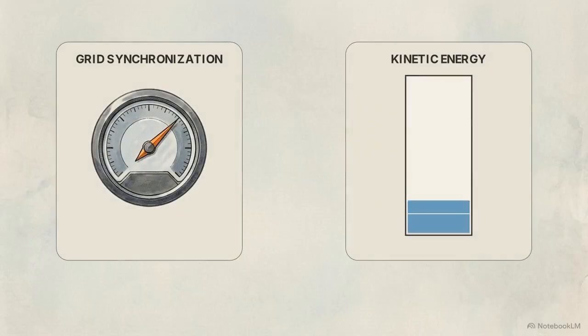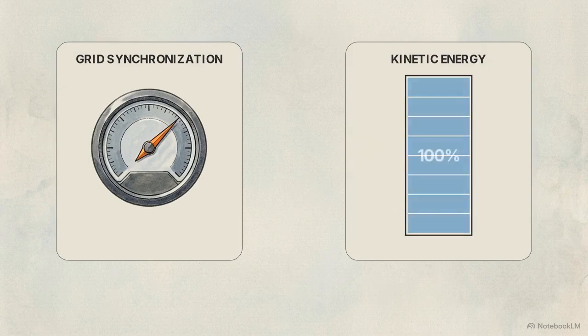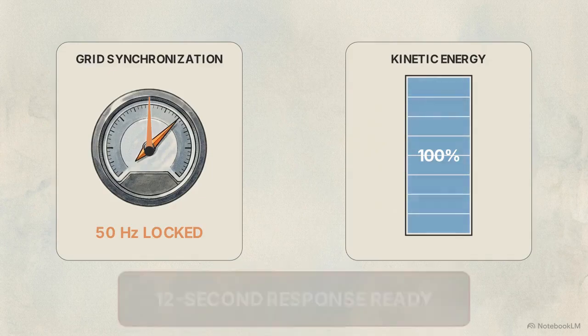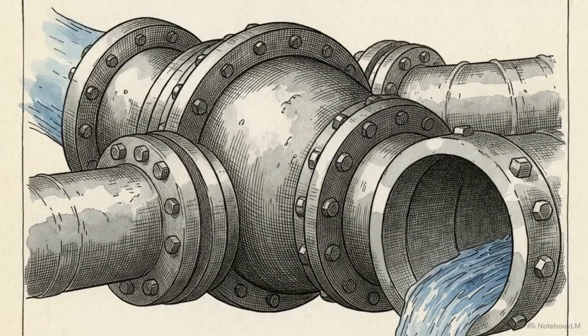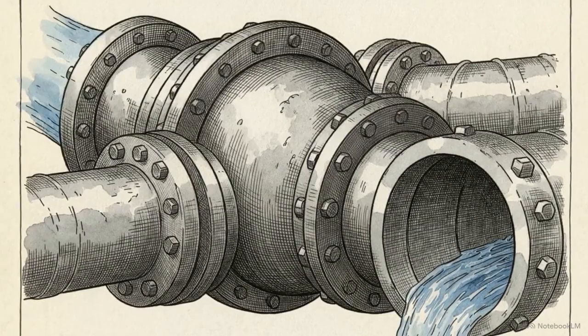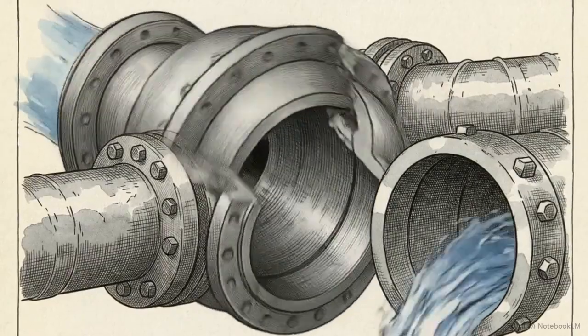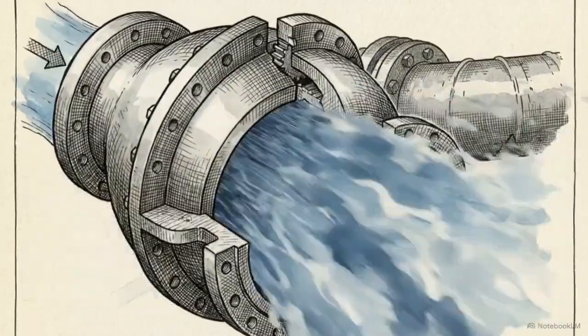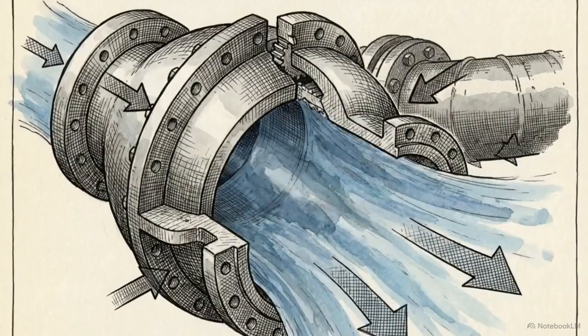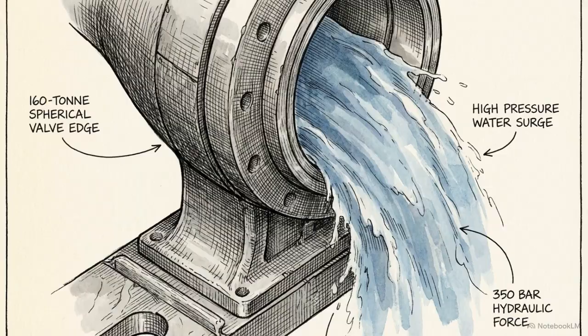By preloading the kinetic energy into the system and maintaining synchronization, Dinorwig circumvents the mechanical startup penalty. This makes a 12-second response physically possible. At the 5-second mark, the station receives an emergency load pickup command. The compressed air vents, and a 160-ton spherical valve rotates open. This component executes the release while holding back water at 80 bar of design pressure.